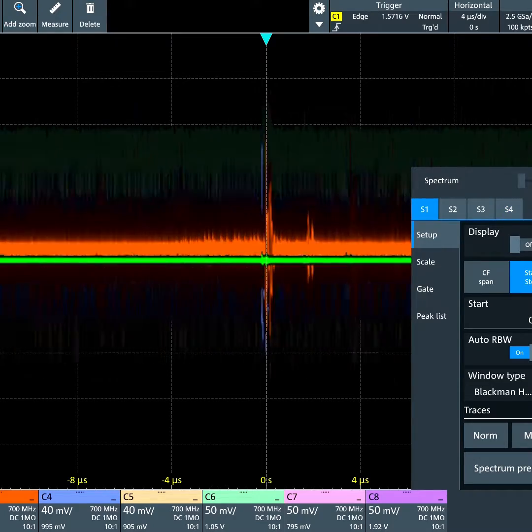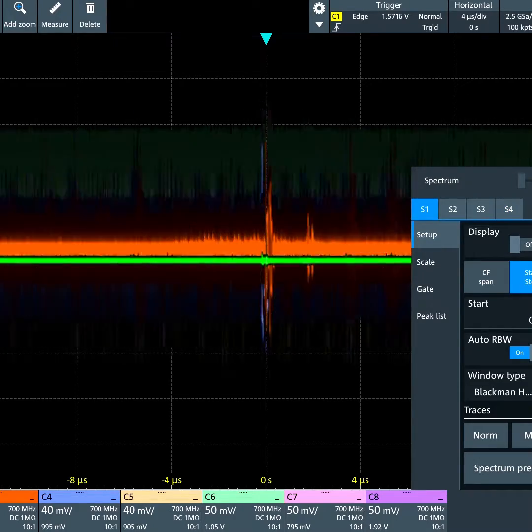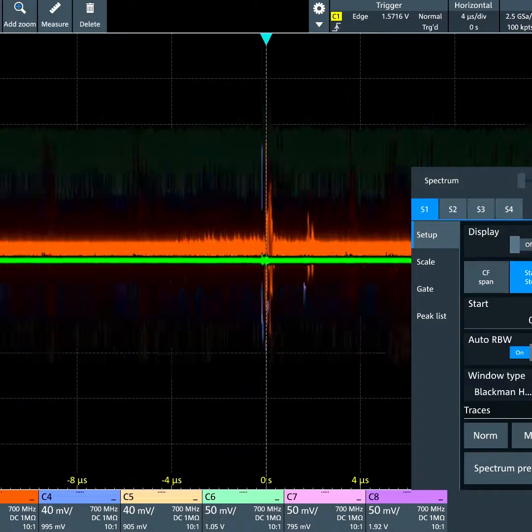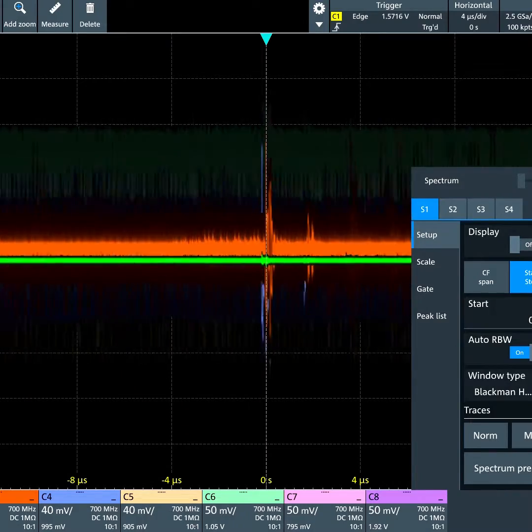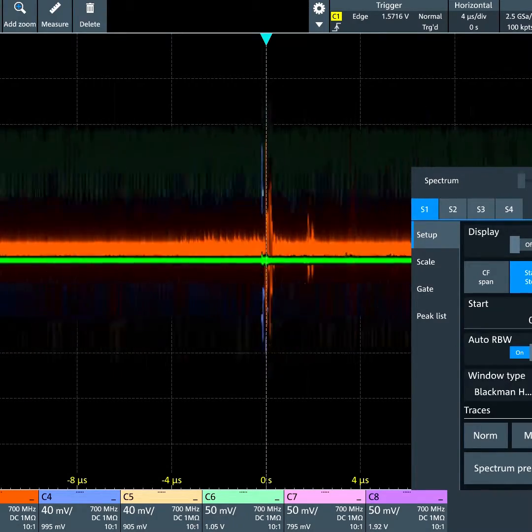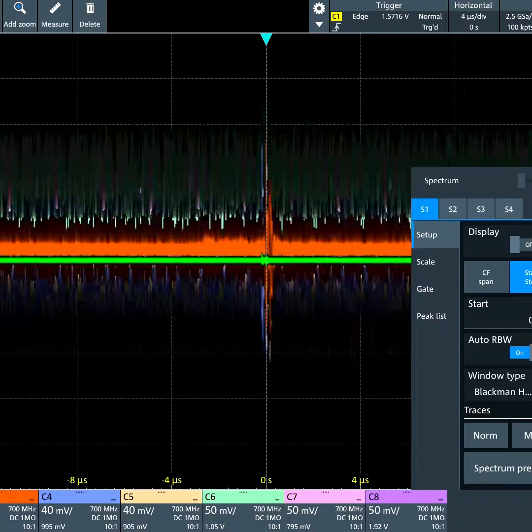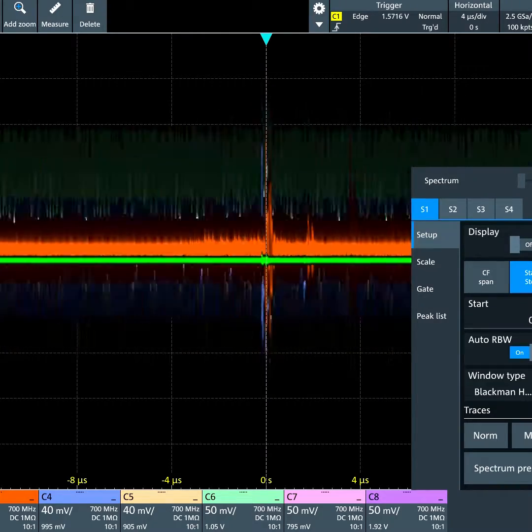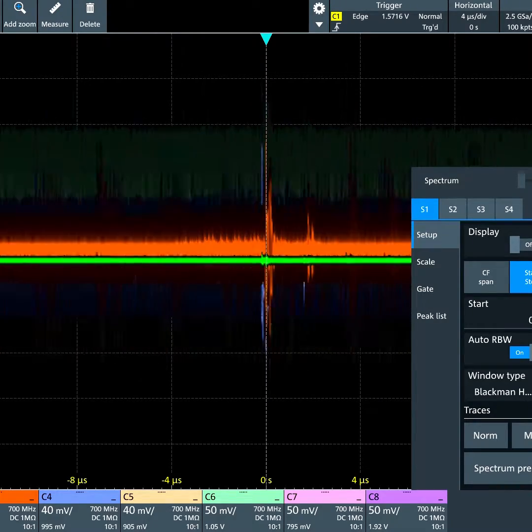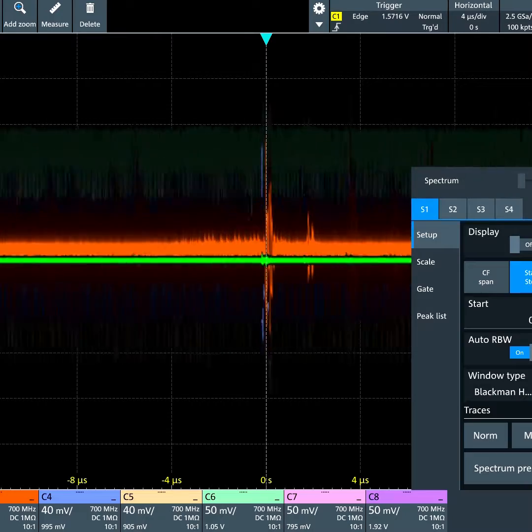Each one can have its own start and stop frequency, resolution bandwidth. They're all independent and in fact also independent of the time per division scale. The FFTs are computed in separate hardware from the display so that you can set them independently.